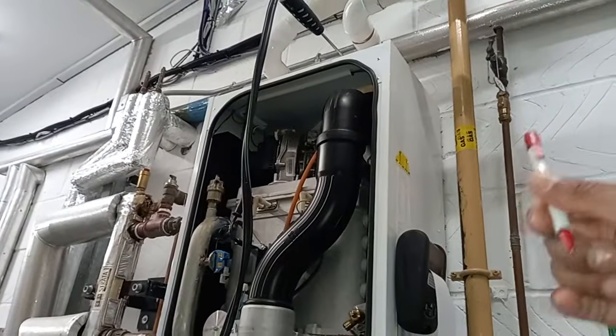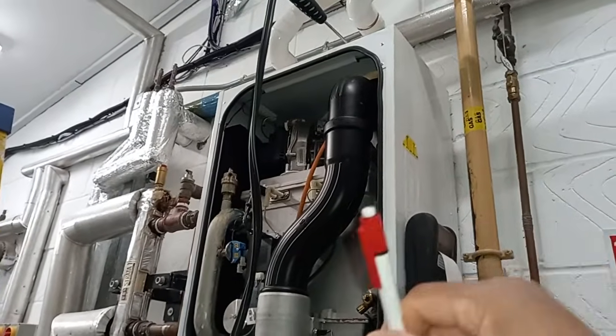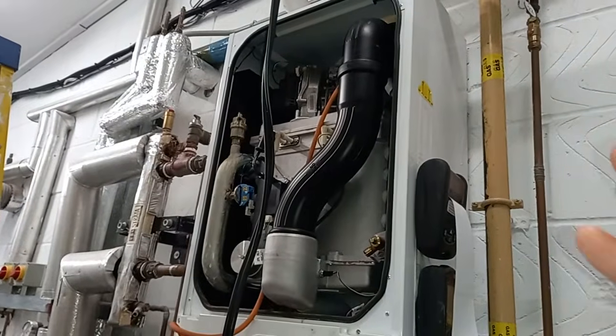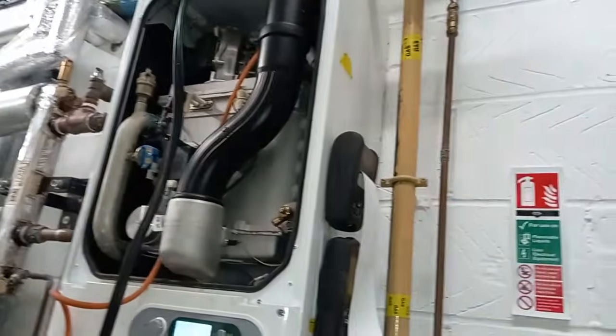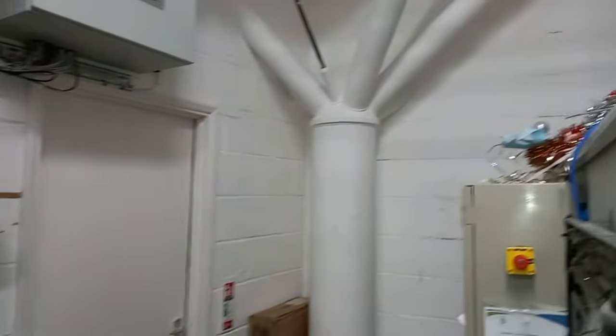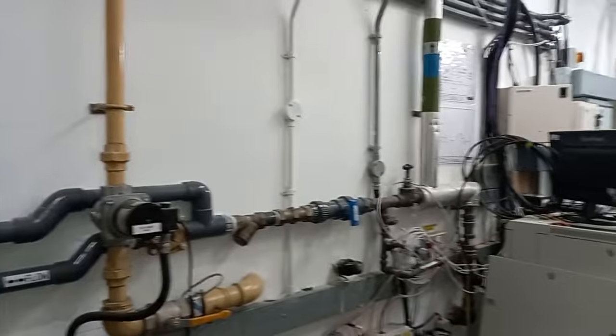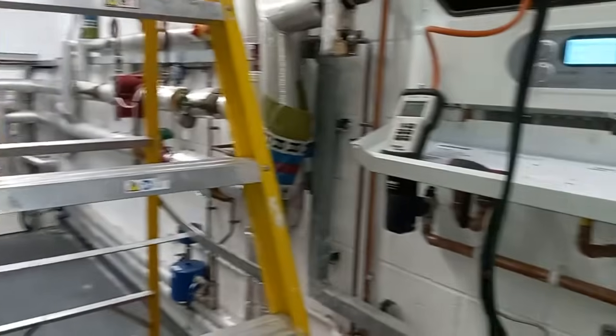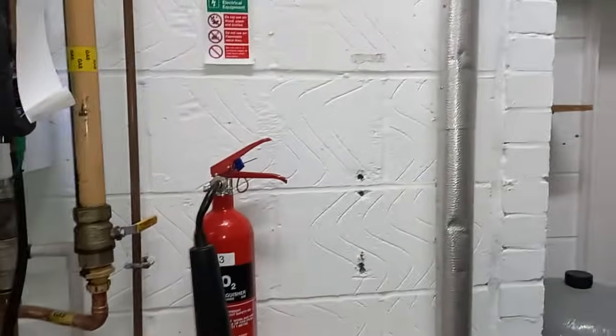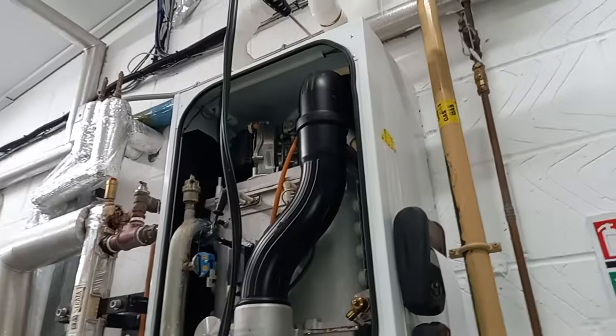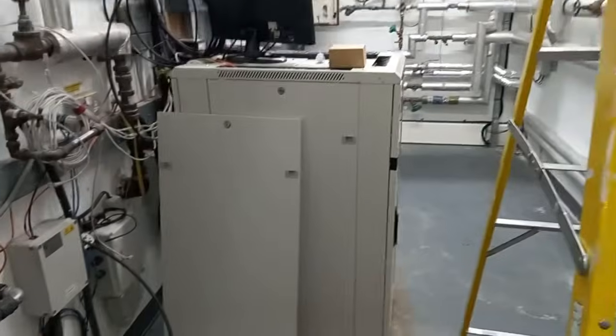Ventilation. This is a room sealed boiler, meaning it takes its combustion air from outside. People get confused about what room sealed means. Open flued means it takes air from the plant room. If this boiler were open flued, I'd want to see good ventilation inside here, but I don't see any proper purpose-provided ventilation for this plant room at all. It's room sealed, so it should still have ventilation, but nowhere near as much as an open flued appliance.